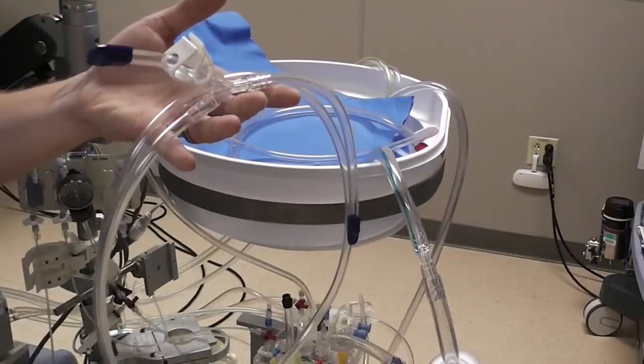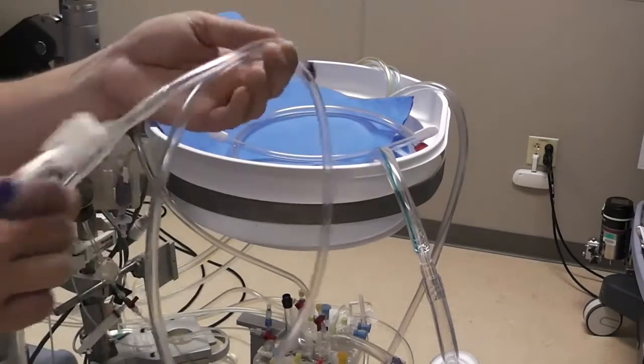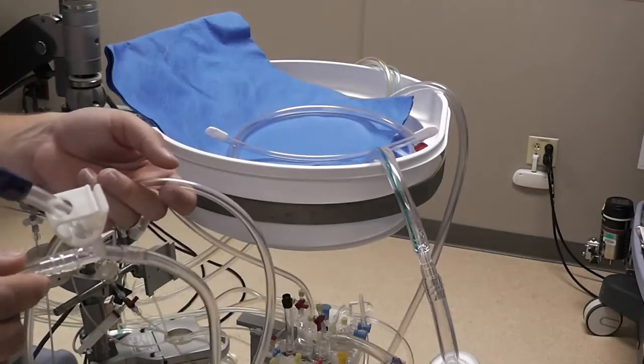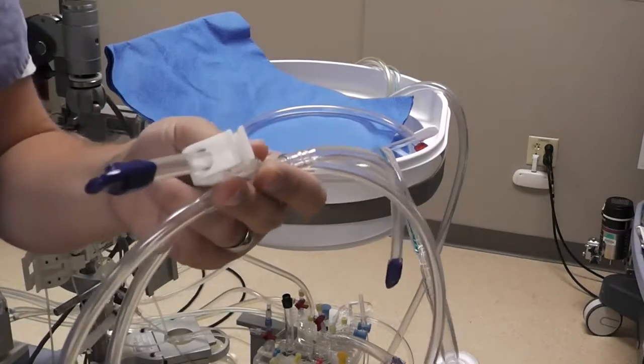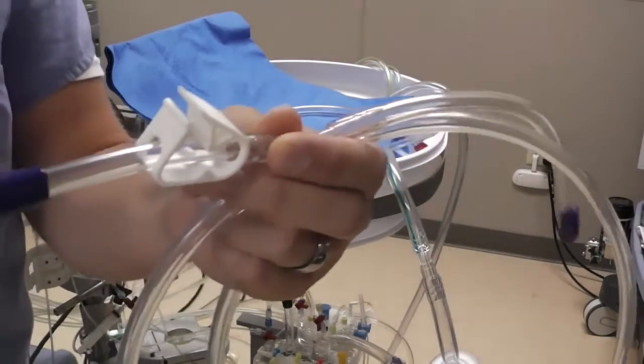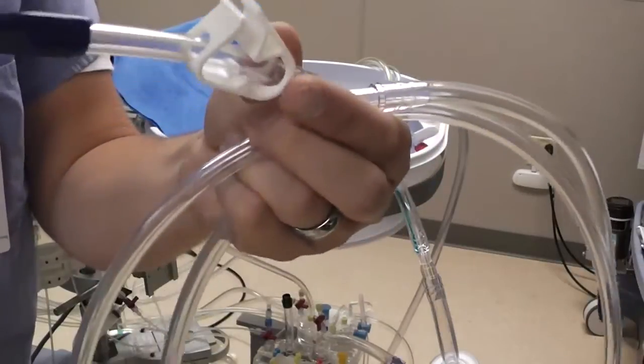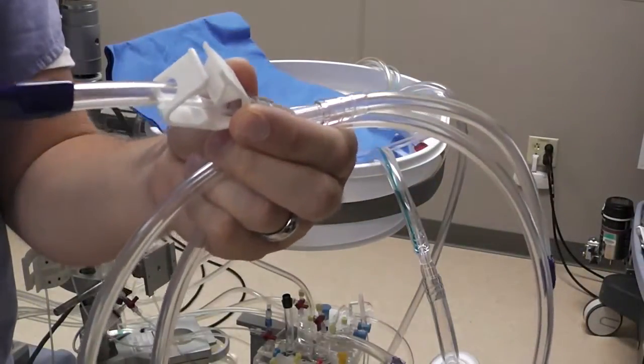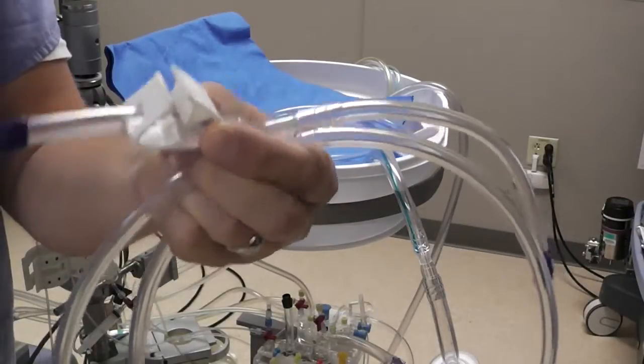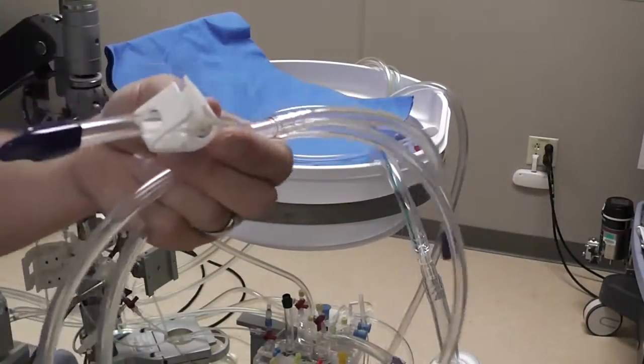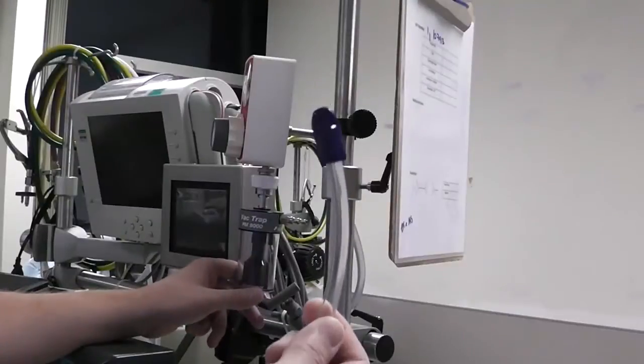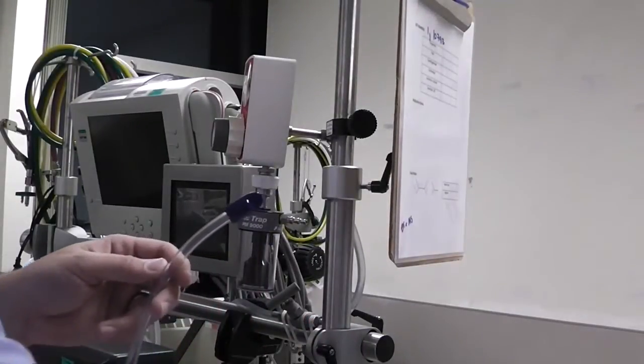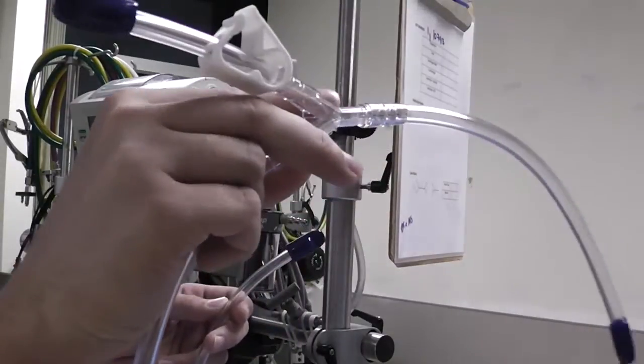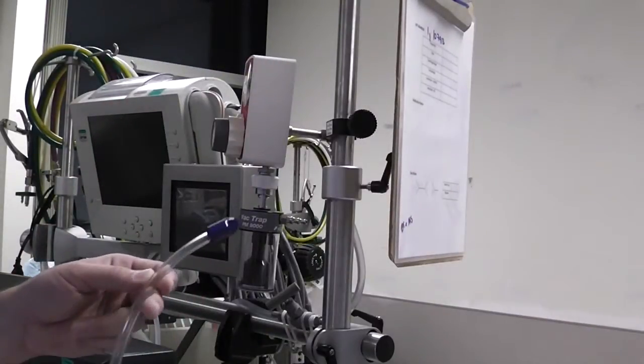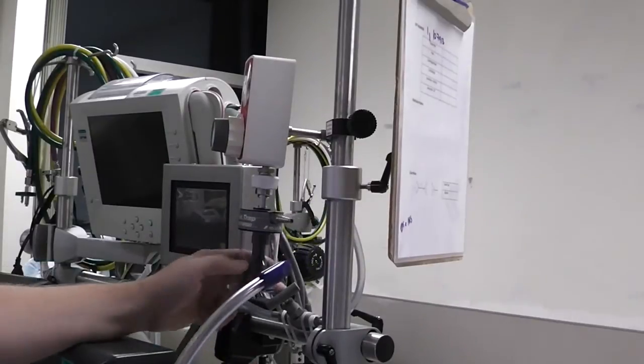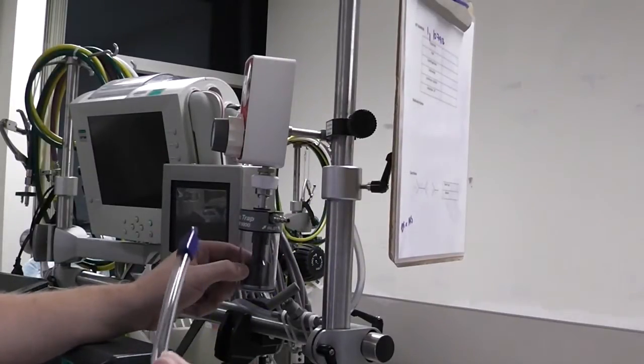Next we're going to attach our vacuum line. This is the one that has the blue connectors all over it, and I'll mention this in the backup section, but just make sure that the Duraclamp on this is open. If this were to be closed and the vacuum regulator were on, you could accidentally put vacuum on your reservoir, which would be bad. So here I have the long end of the vacuum line. You can see the other side has the Y with the little stubby end there. This is the long end, and this is going to attach to the vacuum trap here.